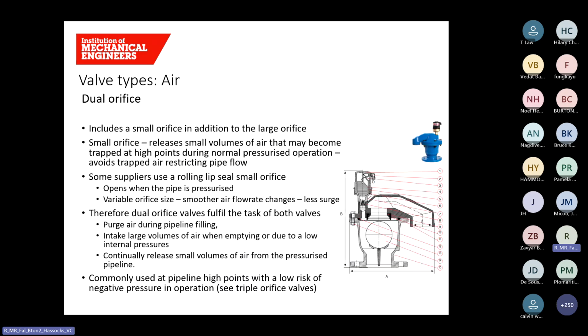The dual orifice air valve consists of a large and a small orifice. So the large allows large quantities of air to escape, such as when filling a pipeline for the first time or during commissioning or after maintenance. But it also allows smaller quantities to escape, and it does so when the pipeline's under pressure. So pumping stations can often release small bubbles of air, and they can accumulate and eventually restrict the capacity of the pipeline. So a small orifice air valve allows this to escape over time. Also, due to being a small orifice, the open and closing time and profile of the air release is slower, which reduces the chance of surge occurring.